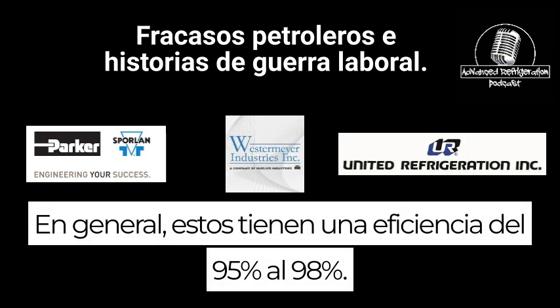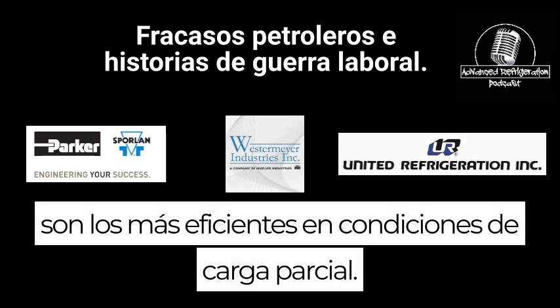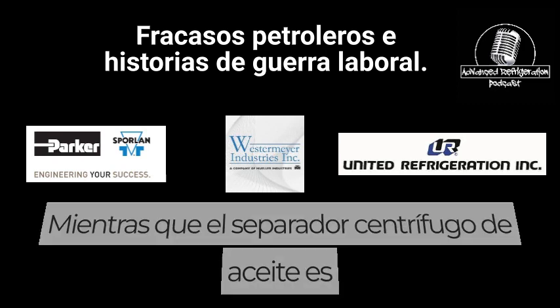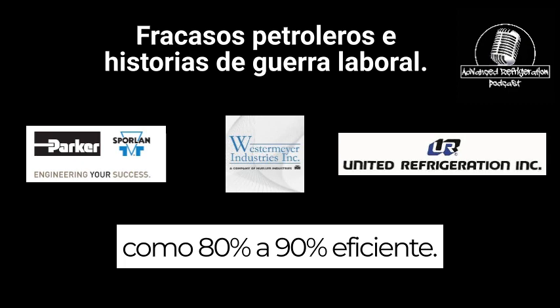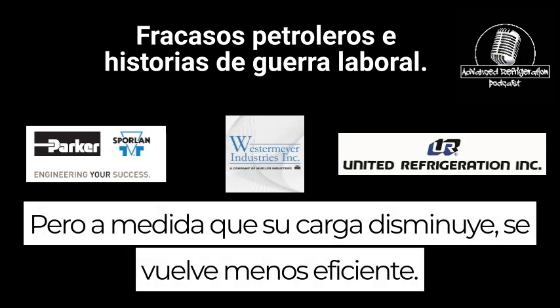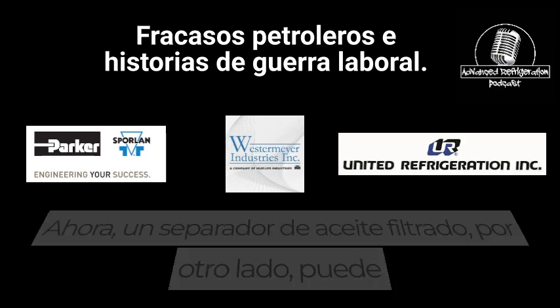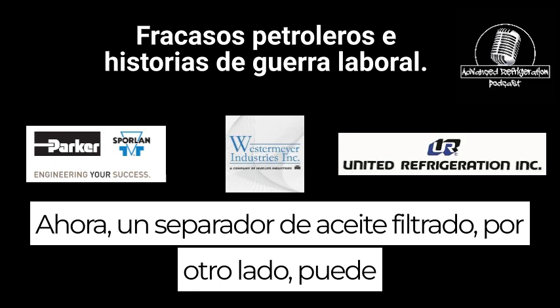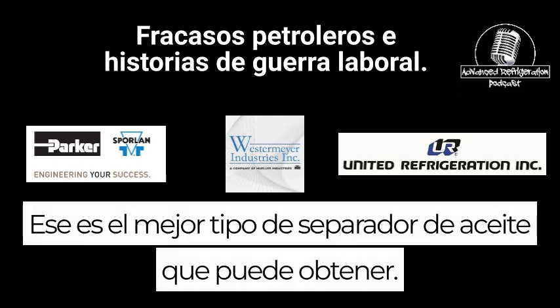Generally, these are about 95 to 98% efficient. They're the most efficient oil separators you get, and they are the most efficient under part load conditions. Whereas a centrifugal oil separator is like 80 to 90% efficient, but as your load drops off, it gets less efficient. So when you're in the wintertime and the head's floated way down, it's less efficient. A filtered oil separator, on the other hand, can handle those load changes much better. So that is the best type of oil separator you can get.